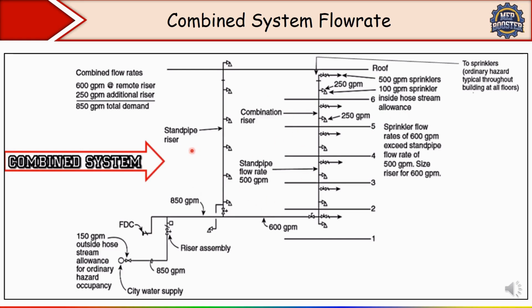So in this case, if you remember, I have discussed here, suppose we have calculated the combined flow rate. Our main target is to calculate the combined flow rate. So first, as I told you, you have to see how to calculate the standpipe flow rate. Simple. For the most remote standpipe system, yes, the flow should be 500 GPM, all of you know, and for additional 250. So here, for the most remote riser, the flow for standpipe is 500 GPM.